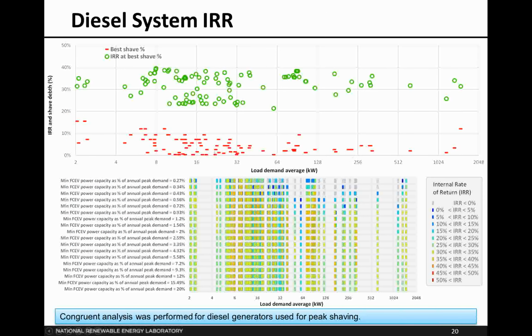Again, depth of peak shaving is in red, and internal rate of return is in green. There is less of a sensitivity to demand size, and the total IRR tends to be a little lower because you're attributing the total cost of the system to peak shaving, whereas if you have a fuel cell, it would have been purchased for moving material through a warehouse, not primarily for peak shaving. So the IRR is a little bit penalized on diesel systems because you have to explicitly purchase equipment for peak shaving applications.